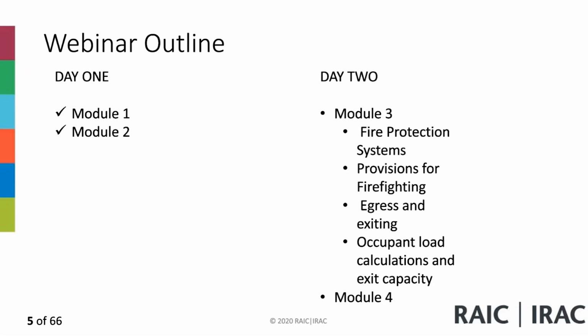And the only time you need to forget about the two major occupancies is if you have them mixed on the same floor, and then the exception for that is 3.2.2.8. But if your whole floor area is considered one major occupancy and the one above is a totally different major occupancy, then 3.2.2.8 does not apply in this case, because they're not mixed on the same storey. Thank you. Okay. Any other question on the quizzes?